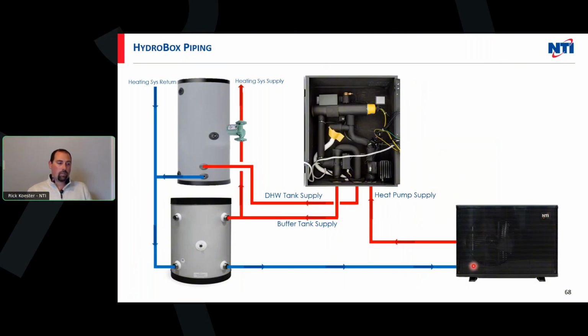Typically, if I'm not using an indirect tank, or even if I am, I may go control box. I can add a diverter valve. I can put my own circulator in place. The internal one is great if I have a short system, meaning I can have the outdoor unit close to home, maybe my mechanical space is right there. There are some little pumps, so we have to think about that when we're designing the system: how far away, how small, how large. So when we size these things, we would love to be part of those conversations to help you.